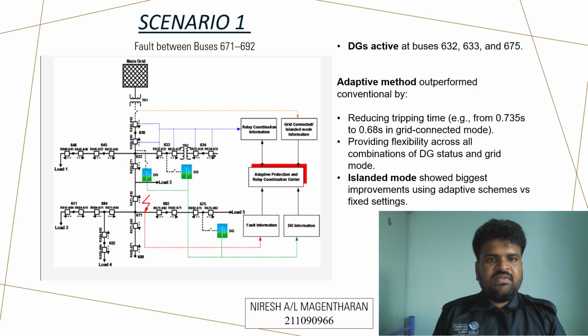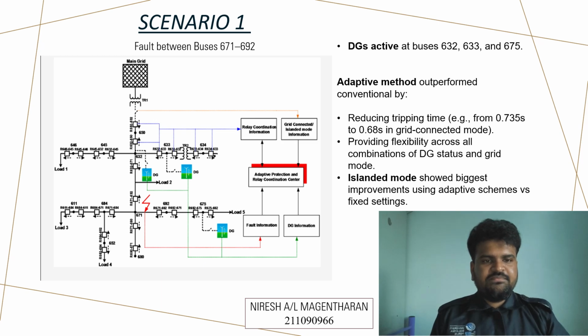Scenario 1, which is fault between buses 671 to 692. DGs active at buses 632, 633 and 675. Adaptive method outperformed conventional by reducing tripping time, example from 0.735 seconds to 0.68 seconds in grid connected mode, providing flexibility across all combinations of DG status and grid mode. Islanded mode showed biggest improvements using adaptive schemes versus fixed settings.